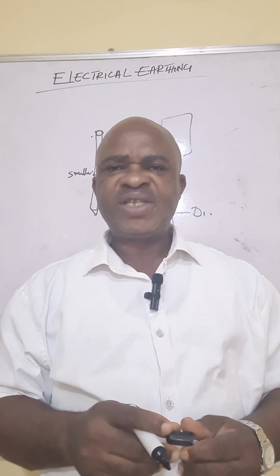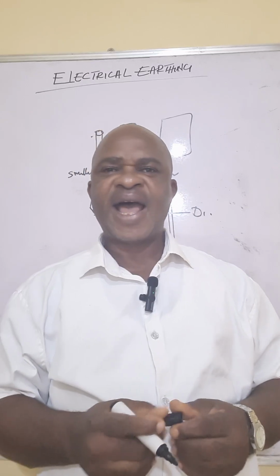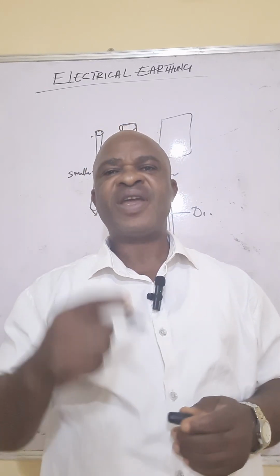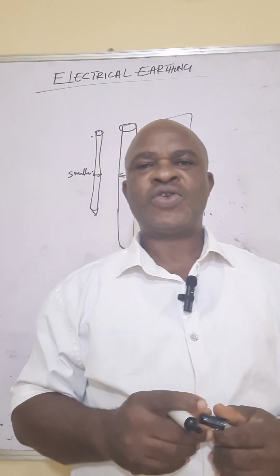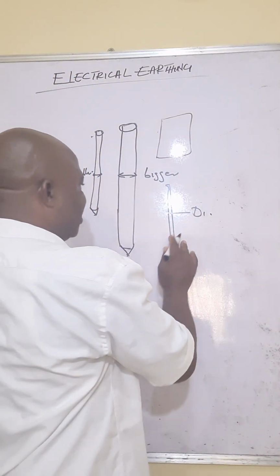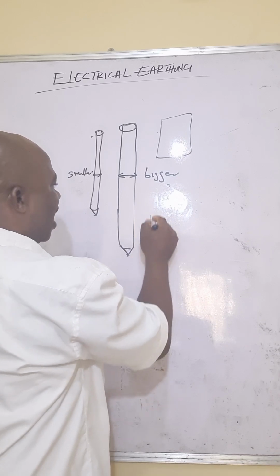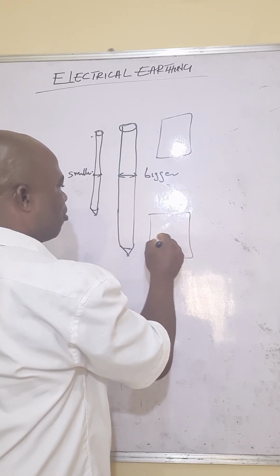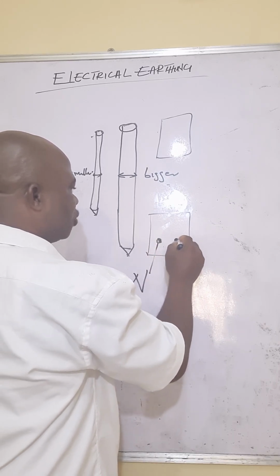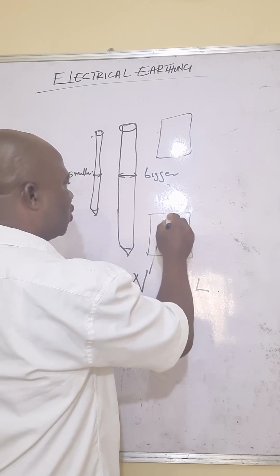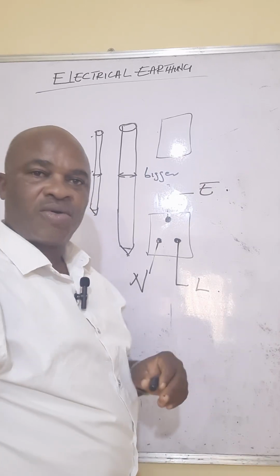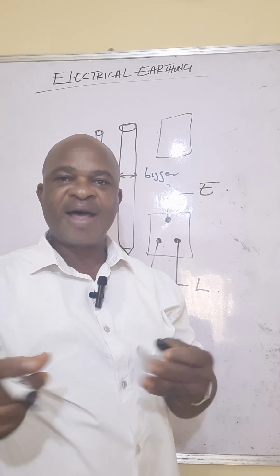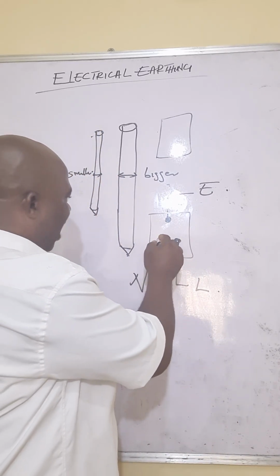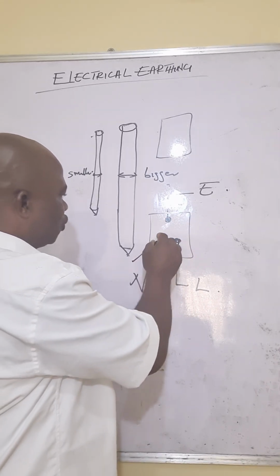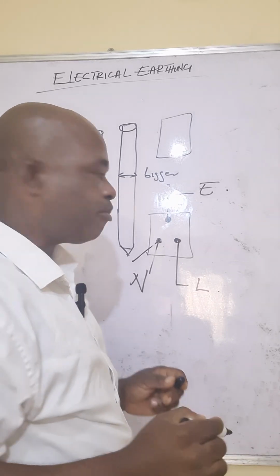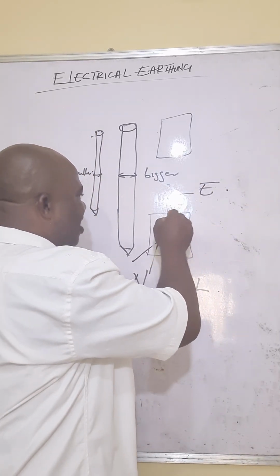Then another important thing which we are going to discuss is, how do you know that your earth is faulty or your equipment or even where you are living is not earthed? See what you do. A socket. Let me take it that this is a socket. Here is port 1, let's call it the neutral end. This is port 2, let's call it the live. And of course, this is your earth, earth E. Now, bring a tungsten lamp, a lamp holder with a bulb. Carry the neutral of this, remove it, and put one of the branches of that lamp holder here. Then carry the other one and put it at this very earth port.